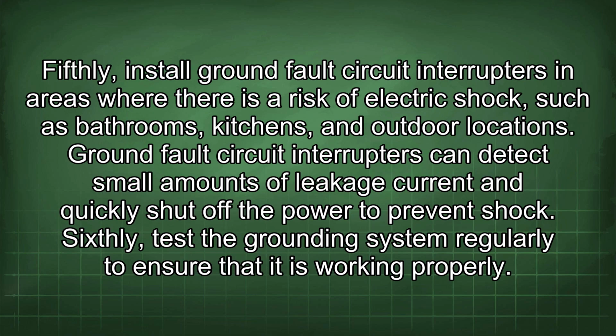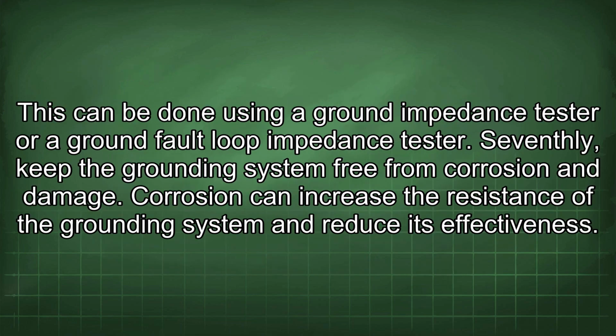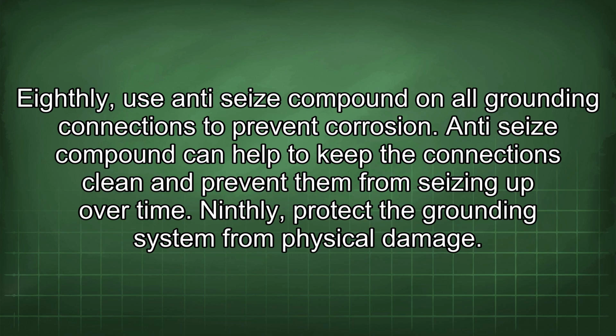Sixthly, test the grounding system regularly to ensure that it is working properly. This can be done using a ground impedance tester or a ground fault loop impedance tester. Seventhly, keep the grounding system free from corrosion and damage. Corrosion can increase the resistance of the grounding system and reduce its effectiveness. Eighthly, use anti-seize compound on all grounding connections to prevent corrosion. Anti-seize compound can help to keep the connections clean and prevent them from seizing up over time.